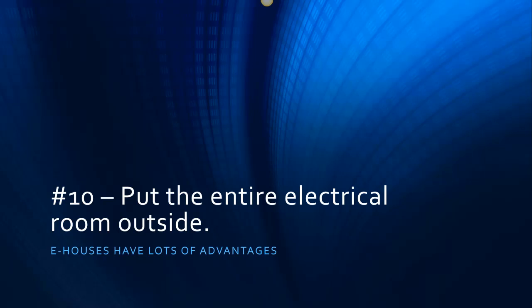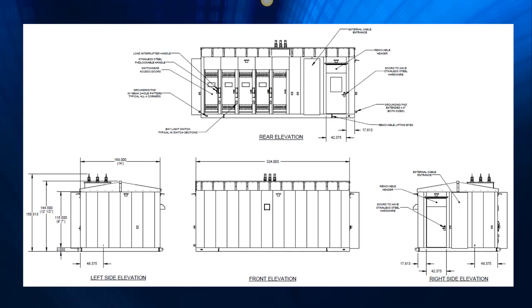So I guess I'm saying here, the best way to save room in an electrical room is to not have an electrical room. There are a lot of advantages to going to an e-house. Here's a typical example. This is a prefabricated electrical house made of metal interlocking panels, or it could be a welded seam building. You see it has switchgear doors integrated onto the rear of this building, and that eliminates all of your requirements for those rear clearances that we discussed earlier. In this particular example, maybe this is going into a substation, it looks like the customer's coming into this building from overhead. So there are overhead air insulated bushings integrated into this particular example.